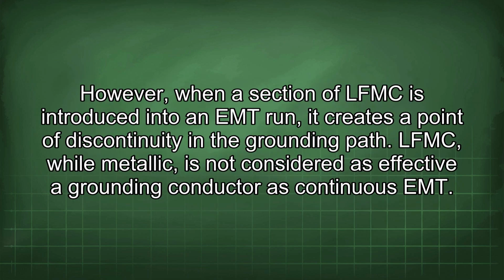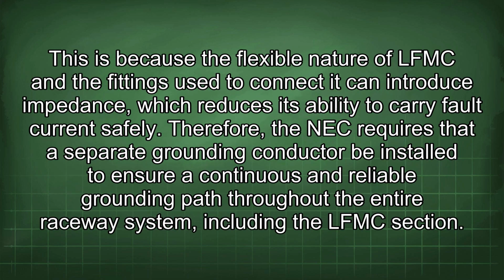However, when a section of LFMC is introduced into an EMT run, it creates a point of discontinuity in the grounding path. LFMC, while metallic, is not considered as effective a grounding conductor as continuous EMT. This is because the flexible nature of LFMC and the fittings used to connect it can introduce impedance, which reduces its ability to carry fault current safely. Therefore, the NEC requires that a separate grounding conductor be installed to ensure a continuous and reliable grounding path throughout the entire raceway system, including the LFMC section.